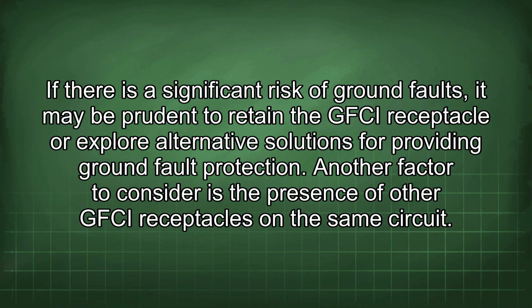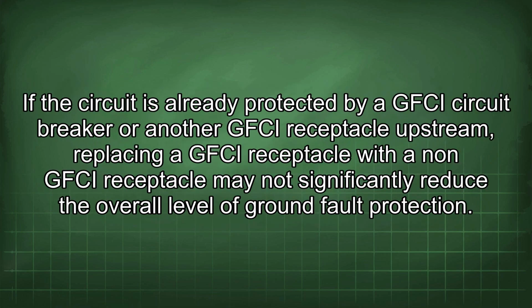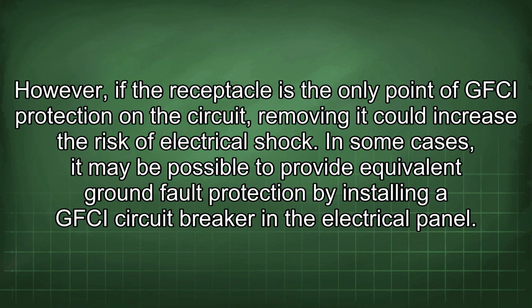Another factor to consider is the presence of other GFCI receptacles on the same circuit. If the circuit is already protected by a GFCI circuit breaker or another GFCI receptacle upstream, replacing a GFCI receptacle with a non-GFCI receptacle may not significantly reduce the overall level of ground fault protection. However, if the receptacle is the only point of GFCI protection on the circuit, removing it could increase the risk of electrical shock. In some cases, it may be possible to provide equivalent ground fault protection by installing a GFCI circuit breaker in the electrical panel.